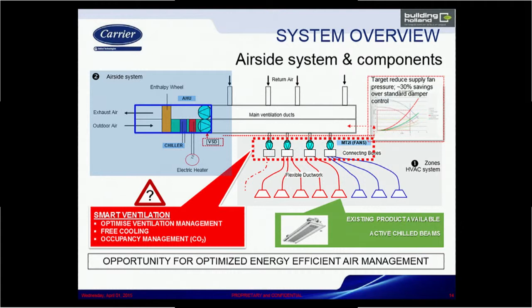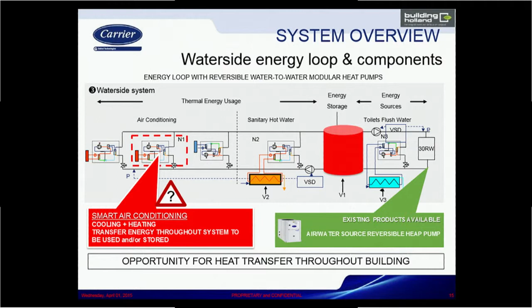On the far right, we have the traditional chilled beam, which we had access to, so there was no issue in terms of providing that part of the system. And the air handling unit itself, as I mentioned, has a heat recovery wheel, and so that's available to us as well. Now on the water loop, there's a little bit more difference here. What you see is a thermal energy loop through the building, broken down into the components of the air conditioning section, dealing with the different zones. Then we have the sanitary hot water section, and then we have the toilet flush system. And in this system here, we introduced energy storage tanks on a floor-by-floor basis. Again, we had the larger air-cooled or reversible heat pump product available, but what we were looking for was a small, smart air conditioning unit, a heat pump unit that could do cooling and heating when needed, but a unit that could move the energy around the building on a modular zonal basis. So we looked at these particular products in terms of our system architecture.